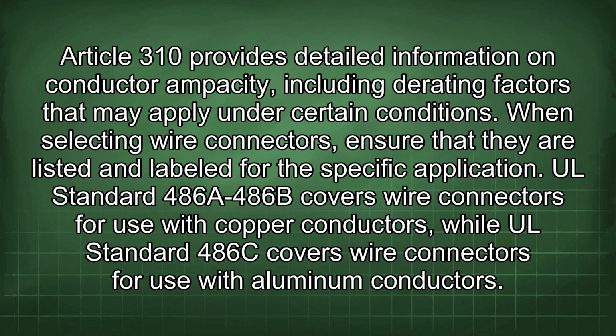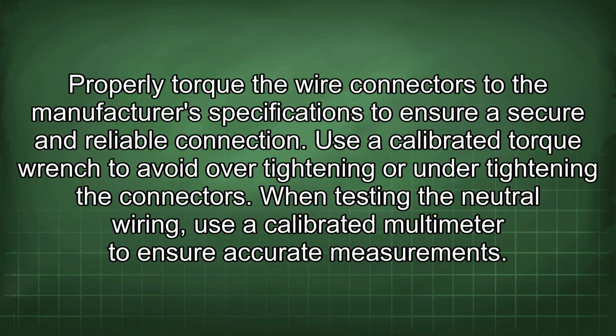UL Standard 486A-486B covers wire connectors for use with copper conductors, while UL Standard 486C covers wire connectors for use with aluminum conductors. Properly torque the wire connectors to the manufacturer's specifications to ensure a secure and reliable connection. Use a calibrated torque wrench to avoid over-tightening or under-tightening the connectors.